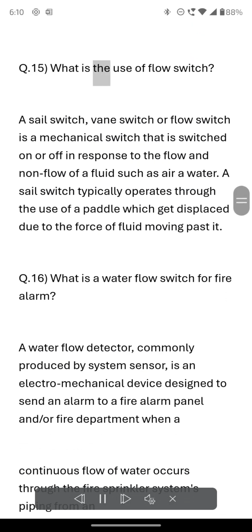Q.15. What is the use of a flow switch? A sail switch, vane switch or flow switch is a mechanical switch that is switched on or off in response to the flow and non-flow of a fluid such as air or water. A sail switch typically operates through the use of a paddle which gets displaced due to the force of fluid moving past it.